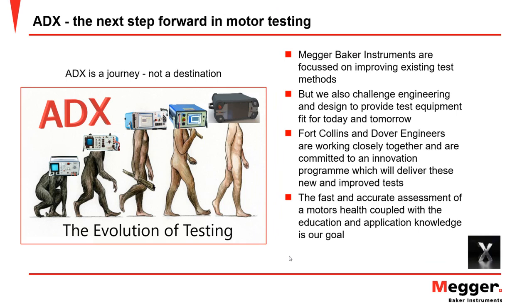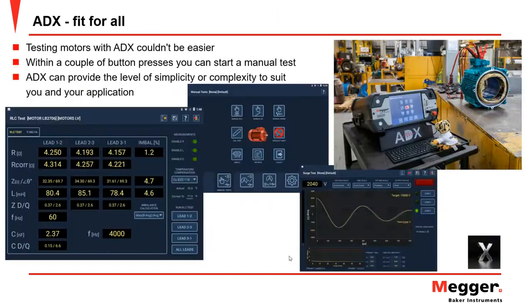That's why we need these bigger units that have the capacitors in the back to fire a pulse at low power to see if there's any weakness between those turns and coils. So that's a little explanation of why they look a little bit different to handheld testers. So this is like the screen of the units. Here we've got resistance, impedance, inductance, capacitance, several results, and we've also got a surge pattern there. That's the waveform. Here we're looking at the inductance of the circuit and the voltage as it dissipates through that circuit. Now we want that to be solid.